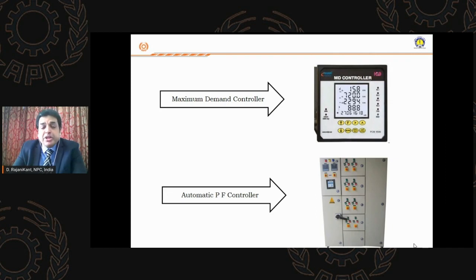And you have automatic power factor controllers. Now, some of the distribution companies will be charging on a kilowatt hour basis, and some of the distribution companies will be charging on a kVAh basis. Whether they charge on a kilowatt hour basis or a kVAh basis, you need to maintain your power factor, that is kilowatt by kVA. If your power factor is less, naturally your electrical bill will be more, then your fuel consumption will be more, and the total energy bill will be more for your company.